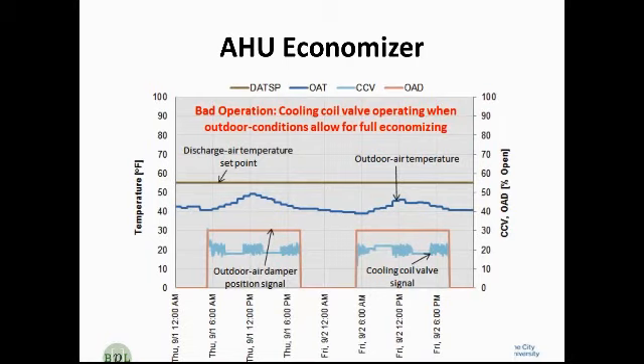But it looks like we've also got the cooling coil valve open. You see the light blue down in the lower portion. The cooling coil valve is open about 20% of the time during occupied hours. So you can see that there's an opportunity here for economizing, and yet we're using our cooling coil valves. Sure would be good to use some economizing here. So obviously we have a good situation here for full economizing because the outdoor air temperature is lower than the discharge air temperature set point. So we really could be economizing here all the time and reducing the amount of chilled water that we're sending into our cooling coils.